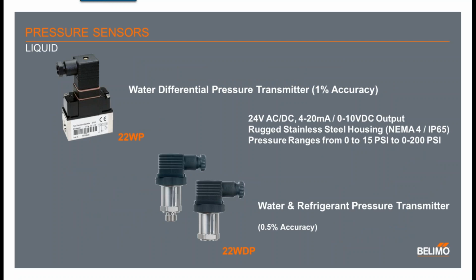Pressure sensors for liquid. We have water differential pressure transmitters and static water and refrigerant pressure transmitters. All 24 volt supply and optional 4 to 20 milliamp and also 0 to 10 volt output. Both are housed in a rugged stainless steel housing, which is NEMA 4 IP65, and are available with pressure ranges from 15 psi up to 200 psi.